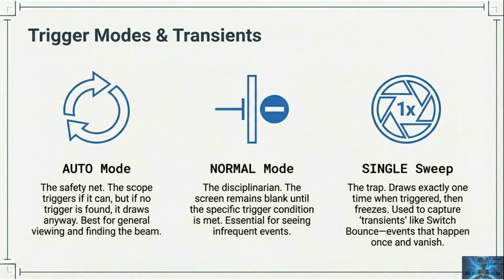Trigger modes and transients. Auto mode is the safety net. If it can't find a trigger, it still draws something so you're not staring at a blank screen. Normal mode is stricter. It won't draw until the trigger condition is met, which is great for intermittent events. Single sweep is the trap. It captures one event and freezes, perfect for catching brief transients like a switch bounce or a one-time glitch.